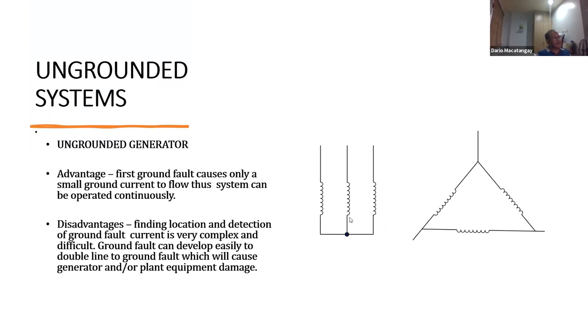So let's say you have a first ground fault. You have a phase ground fault here, for example. The first ground fault will only cause a small current to flow because there are some capacitances to ground. It's coming from the generator itself, from the GSU, from the cable. It's all imaginary capacitance to ground. It doesn't exist, but it's there.